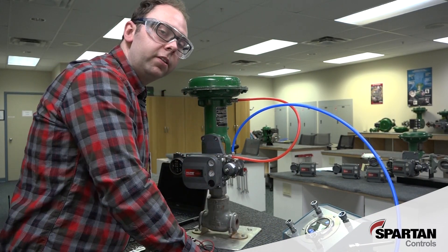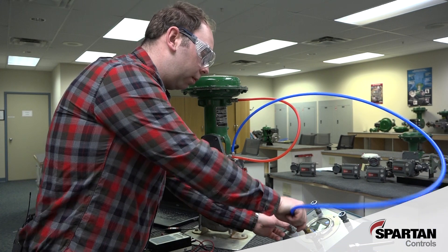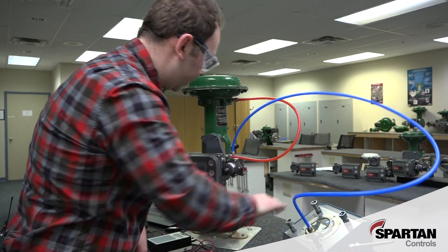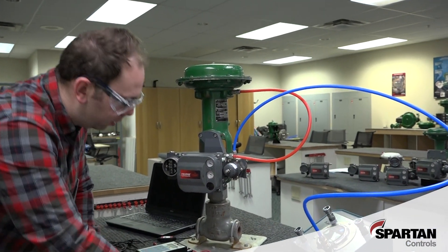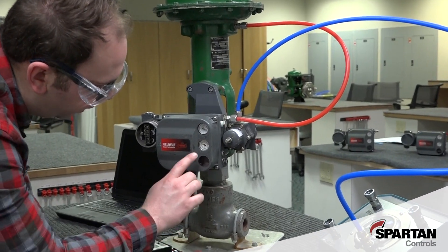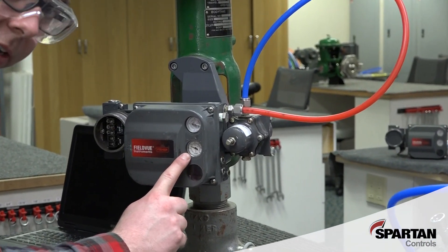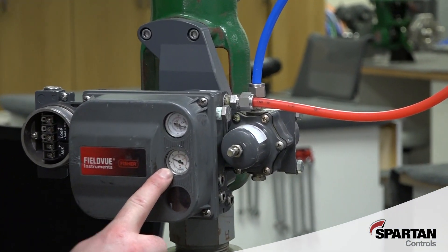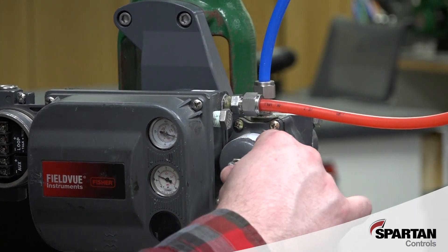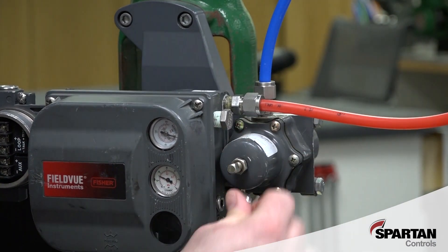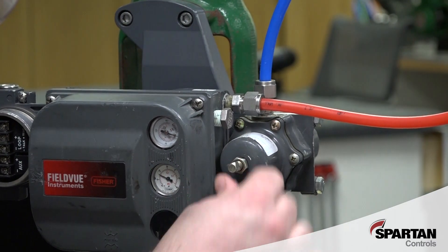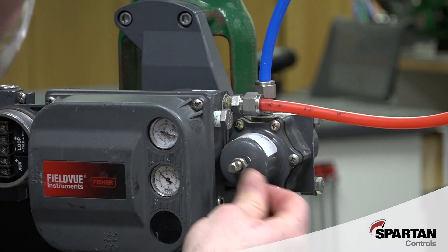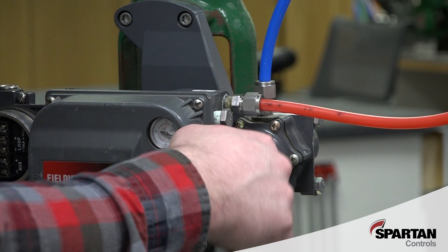With our airlines physically connected to our DVC, we can now apply our supply pressure and then check to see what our regulator is set at. With an operating range of 0-15 psi on our actuator, we're going to want to see 20 psi on our supply gauge. This one right here is set a little bit low, so I'm going to crank up my regulator right now. Looks good. Tighten down my lock nut.